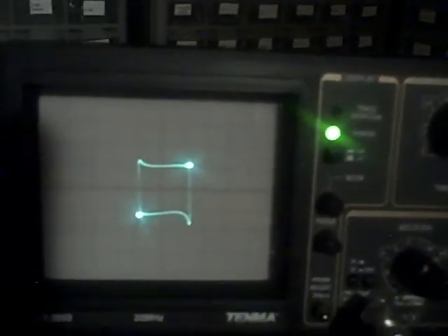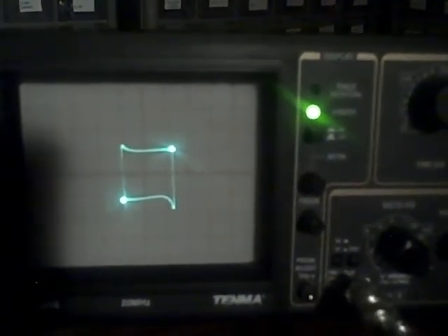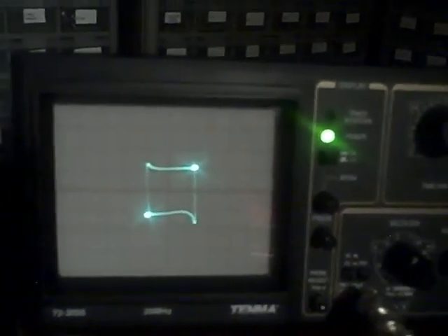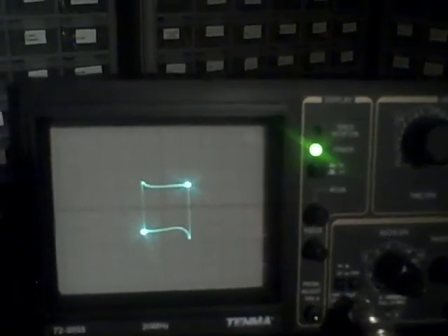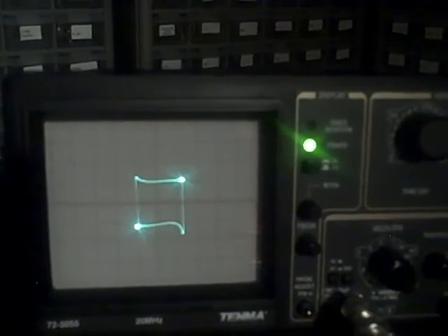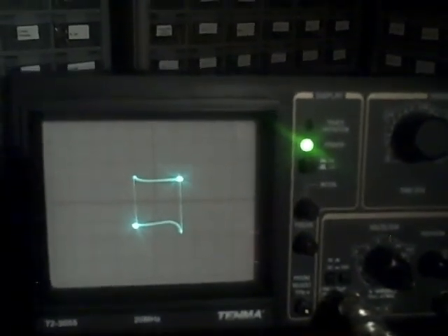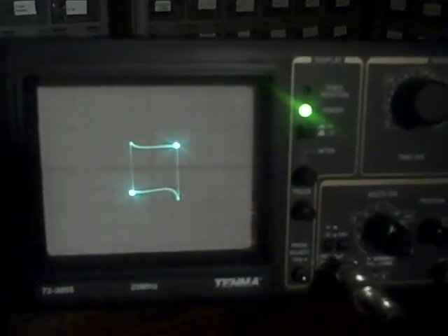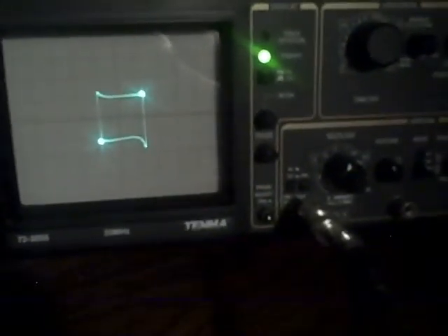We've now stepped through every step of the horizontal range and confirmed that it was reading accurately. So you've got a good time base here on this scope. So now we're going to go and check the voltages on the scope, and if those are correct, time base and voltage would be accurate, and we should be in good shape. And we'll do a little test on that too.